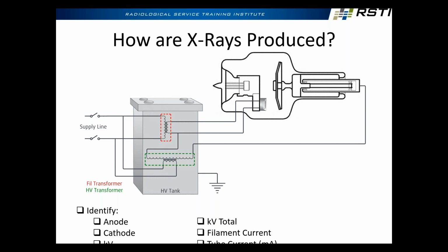So you could equate it to, if you had a piece of sheet metal, let's pretend this is sheet metal, and I was hitting the back of this with a blowtorch, and you saw the metal start to discolor, and the whole time that's happening, the entire sheet is getting hot. It's getting hotter and hotter and hotter, but eventually, right where the blowtorch is hitting, it starts to glow red. You can think of that red glow as being equivalent to the X-ray output compared to the amount of heat that's going into that sheet metal. The metal itself is going to get pretty darn hot. All right.